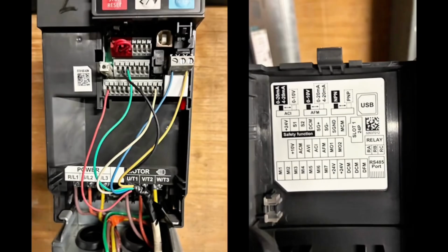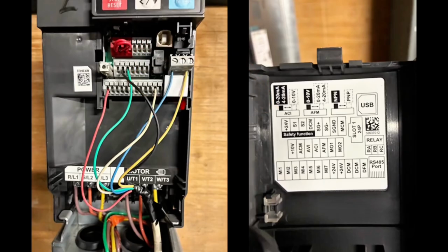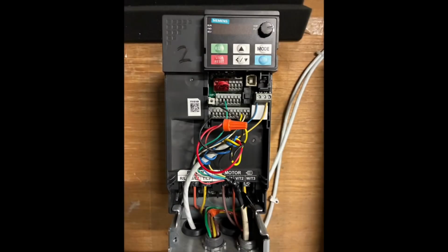So if you look in the back inside cover, not the back cover, the inside cover of the VFD, you can see what each of the terminals is labeled. And this is what it looks like before I installed our wiring. So mainly the wire that tells the VFD to turn on the pumps in a forward direction is that red wire and white wire. That's what we need to tee into, if you will. And here you can see after how I've teed into that.